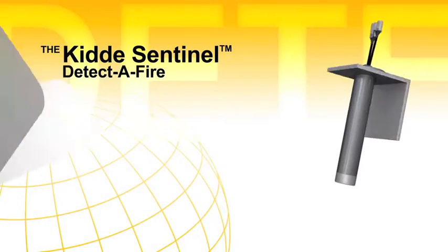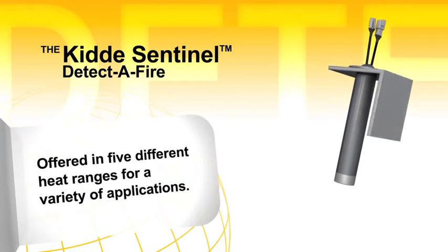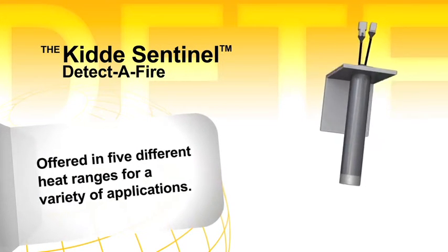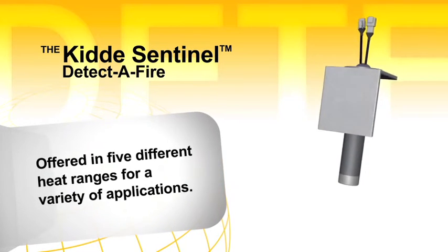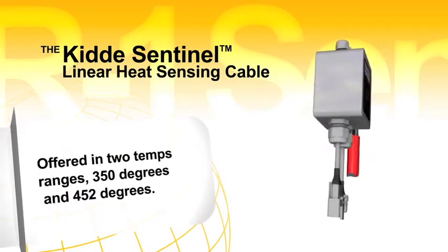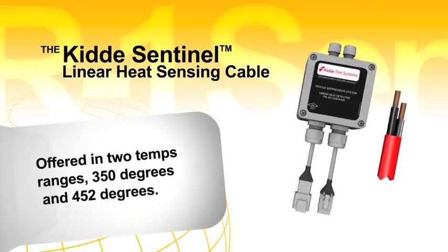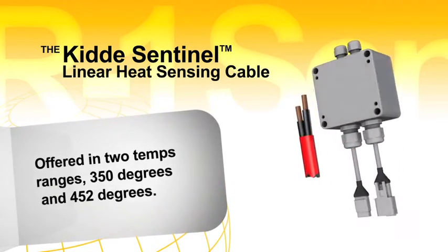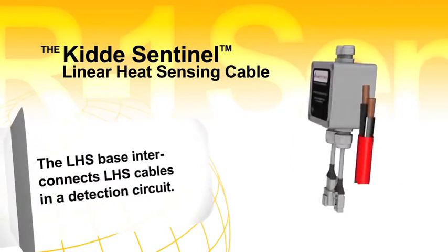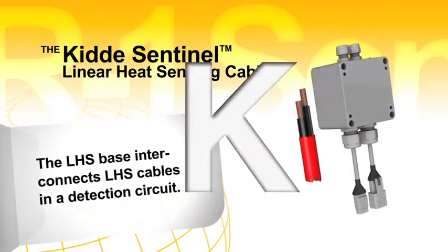The Detect-A-Fire, or DAF, one of the most trusted heat detectors since the late 1940s, has proven time and again that it is the most reliable spot type heat detector on the market. The linear heat sensing cable, or LHS, provides an economical means of detecting heat along the entire length of a wire, and when exposed to the predetermined temperature range, it melts the two conductors together sending a signal to the Sentinel control panel.